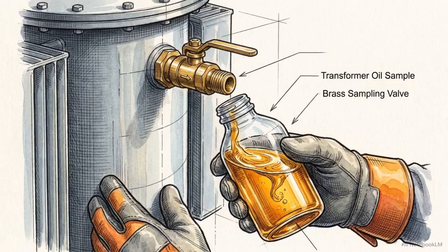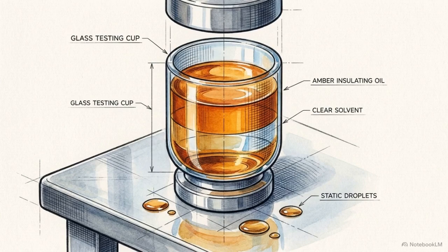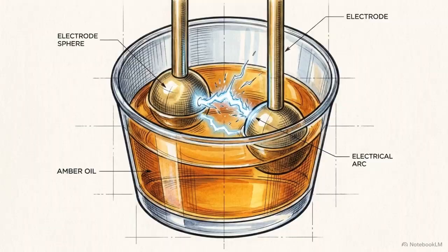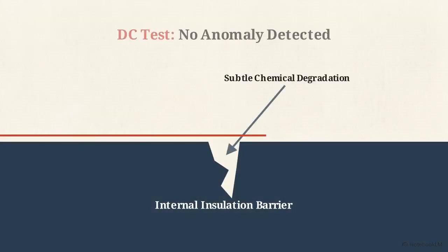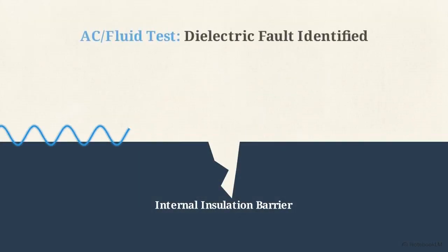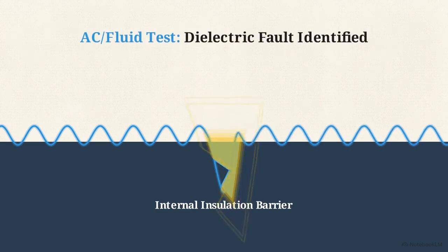Technicians also draw samples to test the oil dielectric breakdown voltage. This requires purging the test cup with a hydrocarbon solvent, eliminating microscopic air bubbles, and applying an escalating voltage ramp until the fluid arcs, which must occur above a 50 kV threshold. Fluid and capacitance testing catches subtle chemical degradation that solid DC resistance testing is entirely blind to.